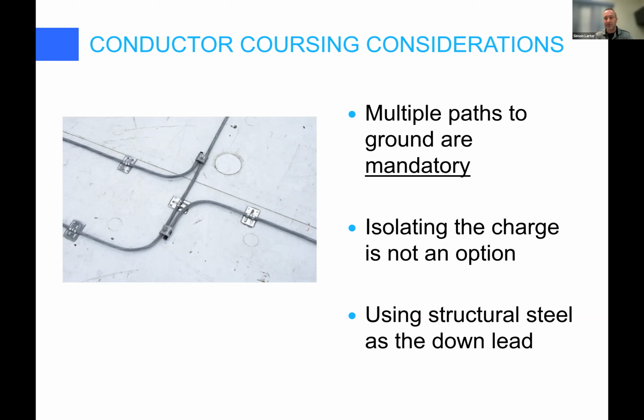You can see the lightning protection cabling is bare. It's not sheathed. I know of one international manufacturer that makes a sheathed, like a triaxial lightning protection cable. We don't use that. In North America, primarily what we use for the lightning protection is a bare copper or aluminum conductor, or tin-coated copper in some instances. So we don't isolate the charge from the building. We have to work with the building, not try and separate ourselves from it. And again, I did mention earlier on, you can use structural steel as the down conductor if the steel is thick enough. And again, 4.8 millimeters, I usually round up to 5. That 0.2 millimeters doesn't make much of a difference. So 5 millimeters thick, if the steel is that thick, you can have that carry the charge.